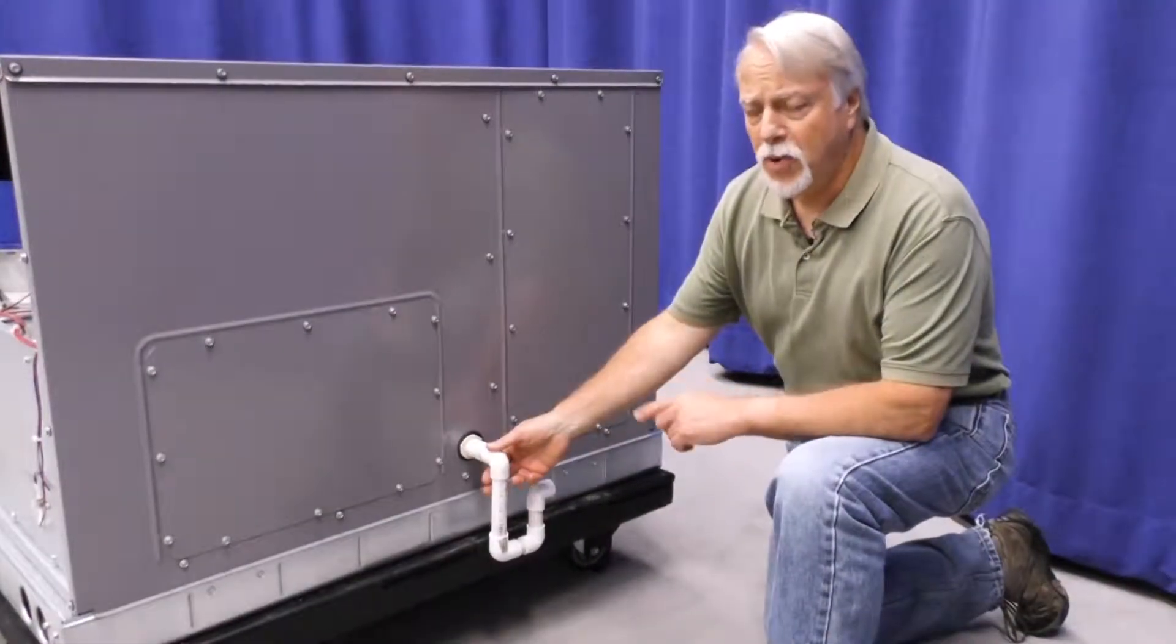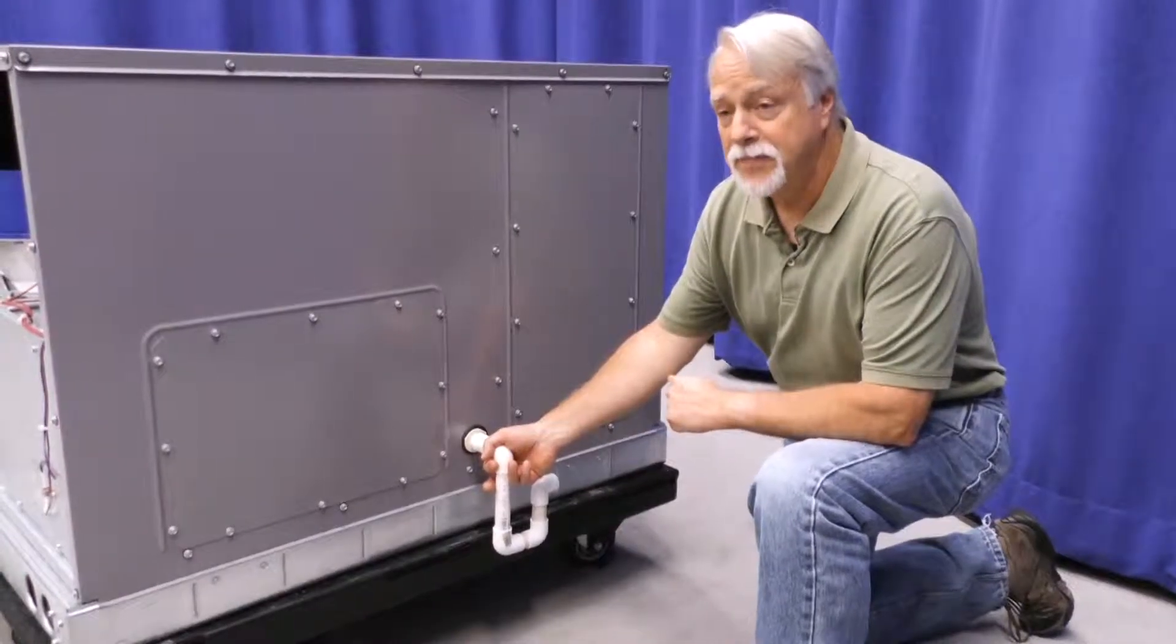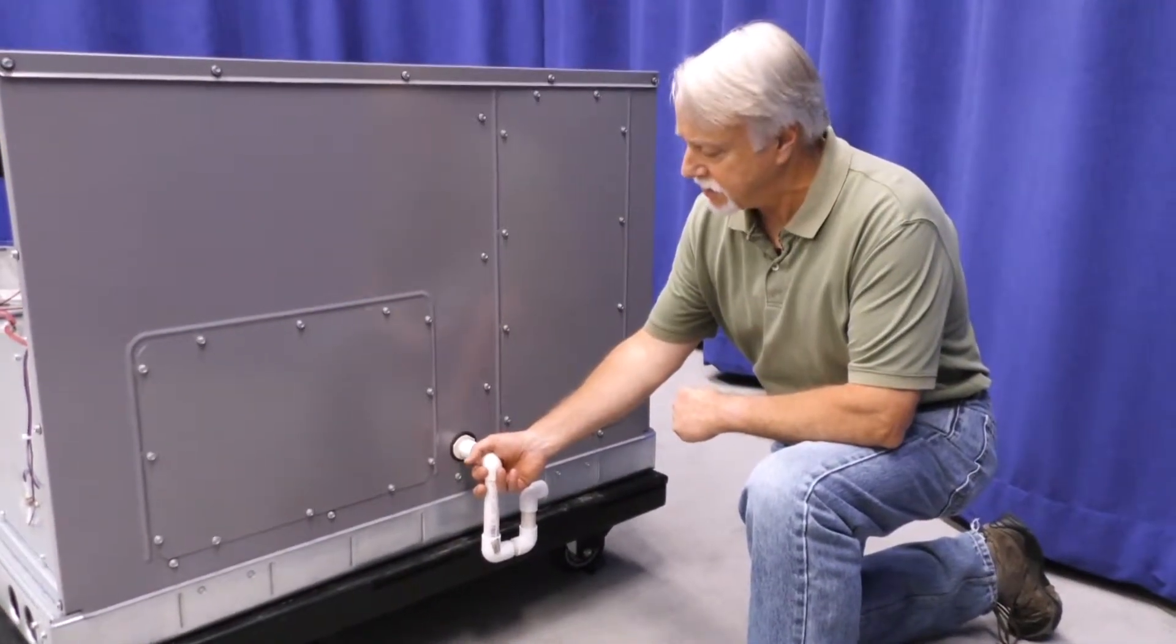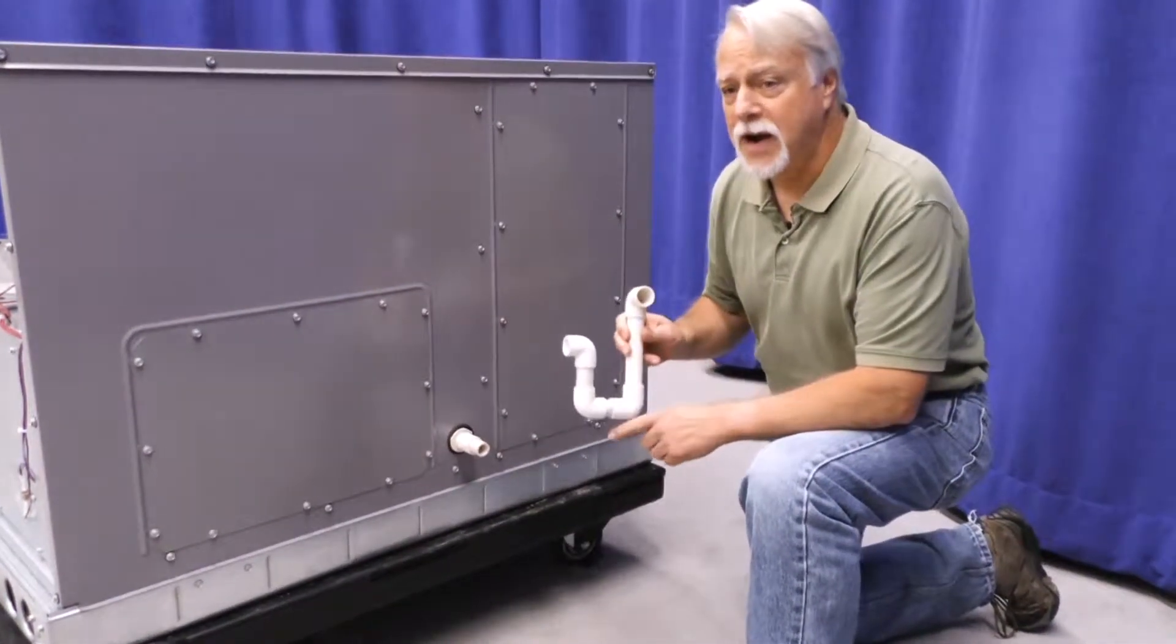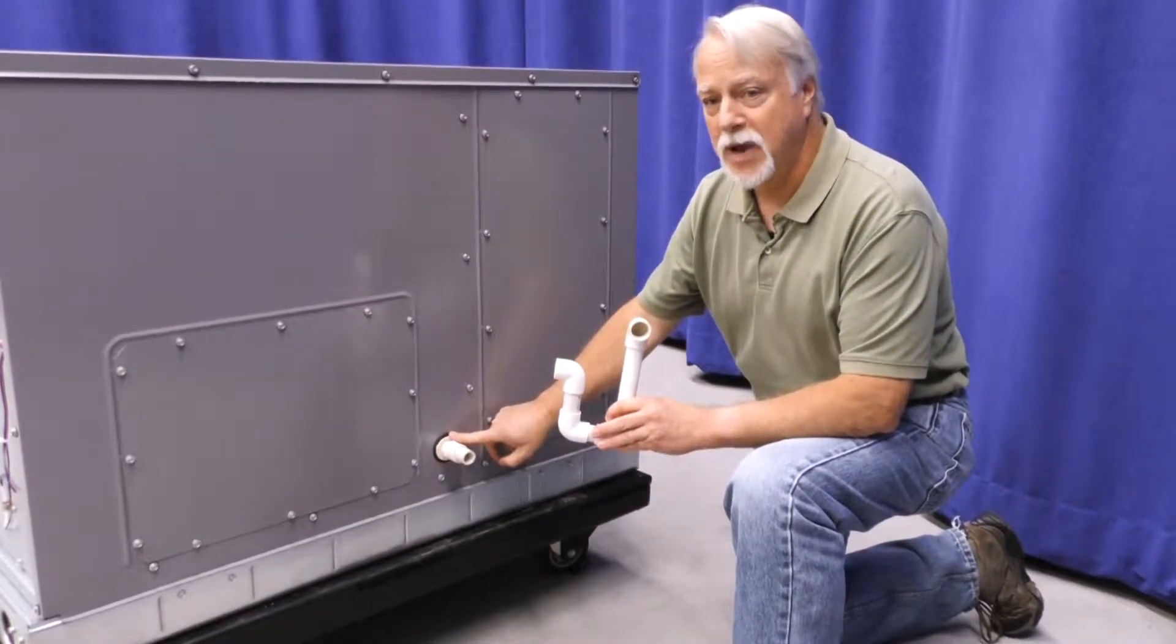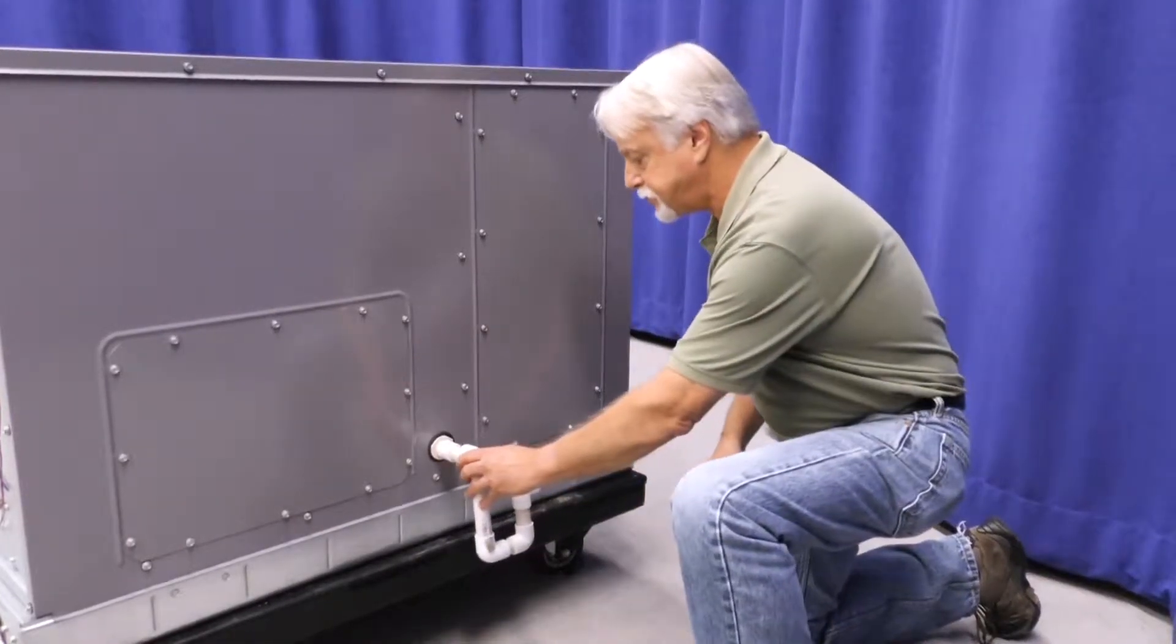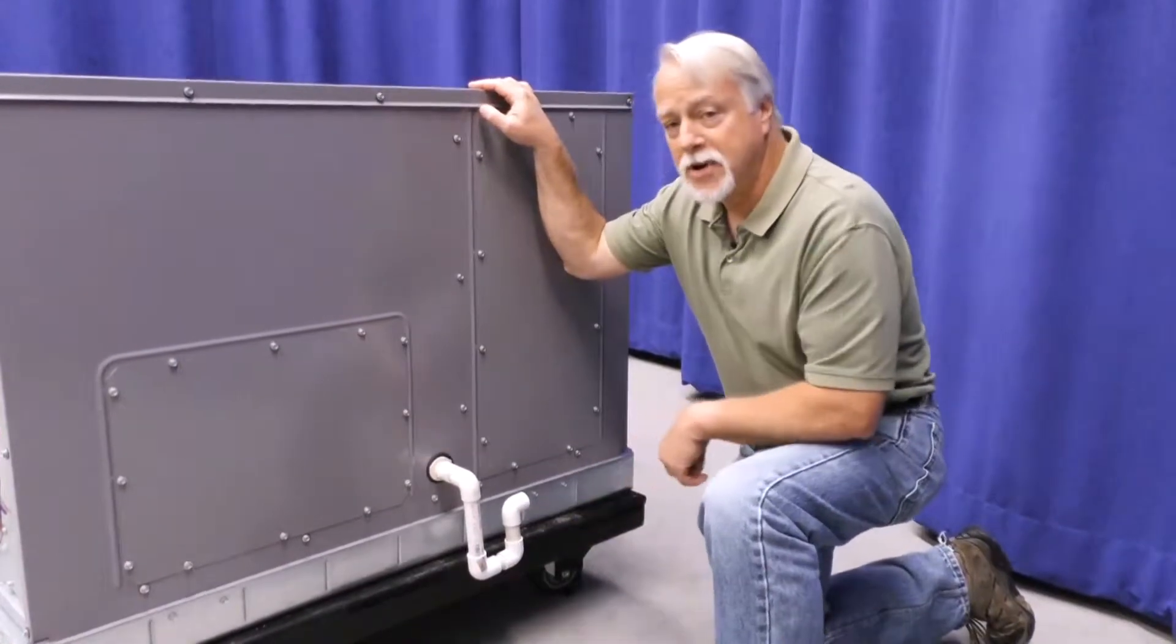It's important to note that every unit requires an external trap, and that that trap be built using the dimensions in the installation instructions. Additionally, it is important to note that the trap is a service component. Ultimately, just like the condensate pan, this will require some level of cleaning or maintenance. Consult the installation instructions for the proper dimensions.